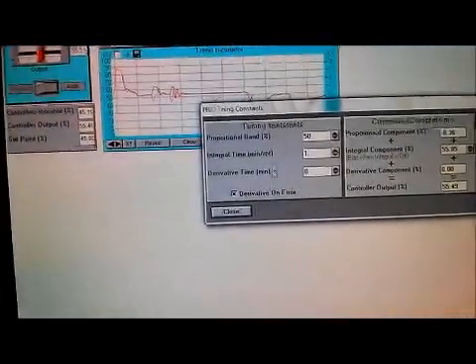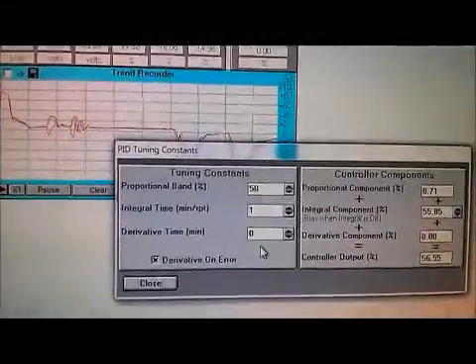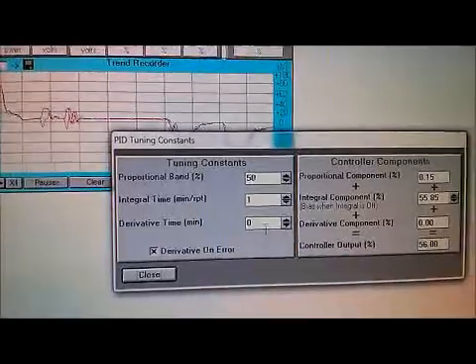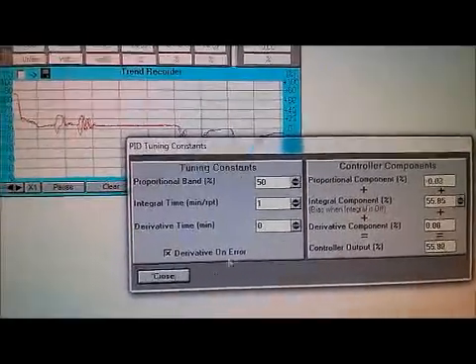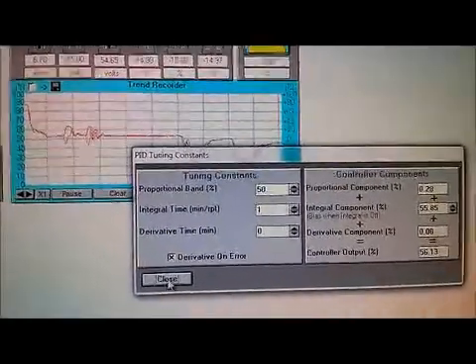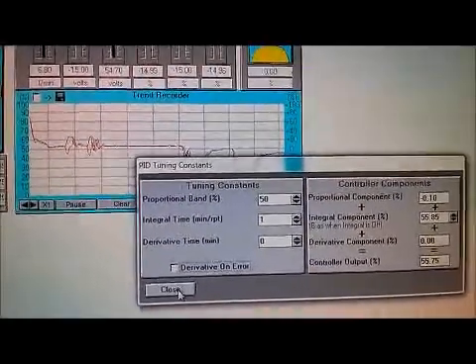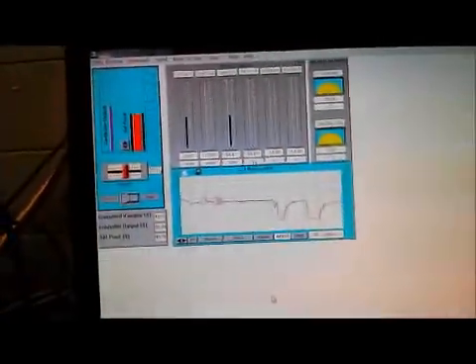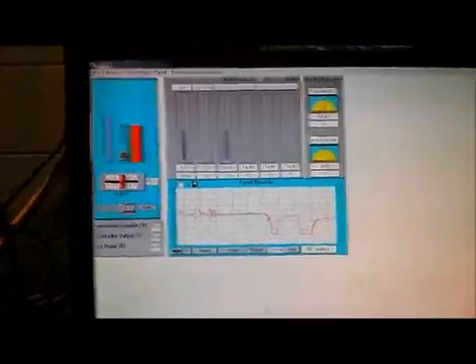For my flow control, which is my slave, I've got 50% proportional band, one minute per repeat. No differential. I guess this doesn't have any meaning because there's no differential. I want PI's good enough for my slave.